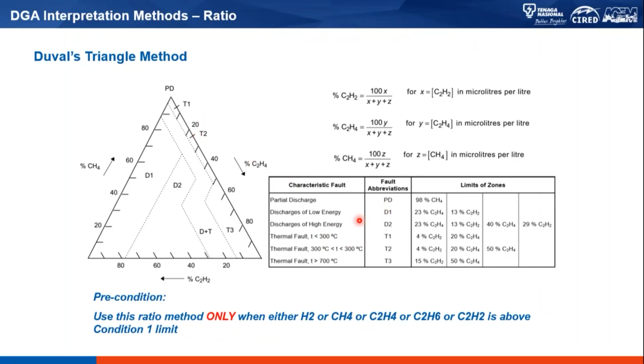One thing to remember: all these ratio techniques we are discussing can only be used when one of the gases is above or outside the limit. Whenever it is below the limit, you should not use this ratio, because it's garbage in, garbage out - it will still point out a fault even though there's actually no fault. So use this whenever it is out of condition, whether you use the IEEE limits or your own limits. Whenever it's out of norms, you can apply these ratio techniques to tell you the characteristic of the fault.